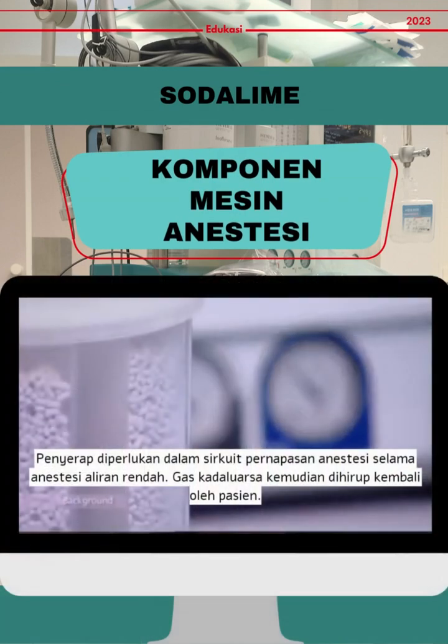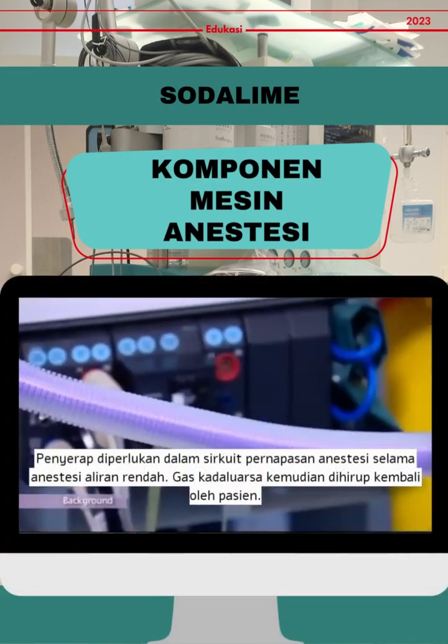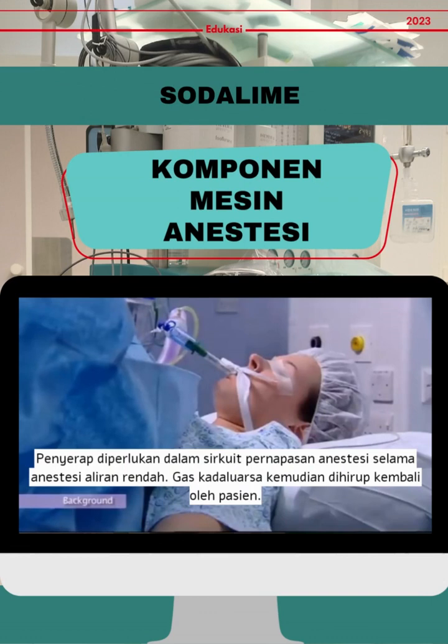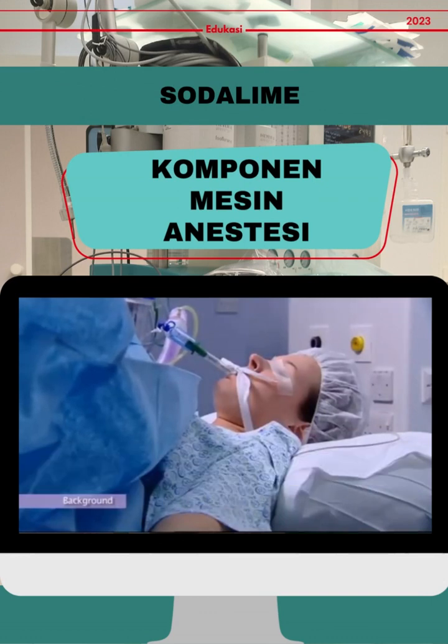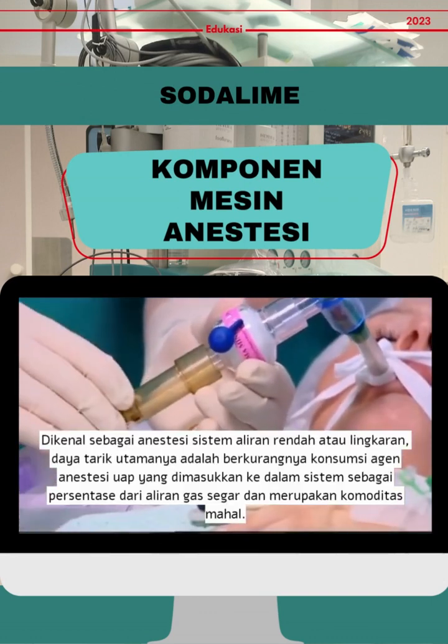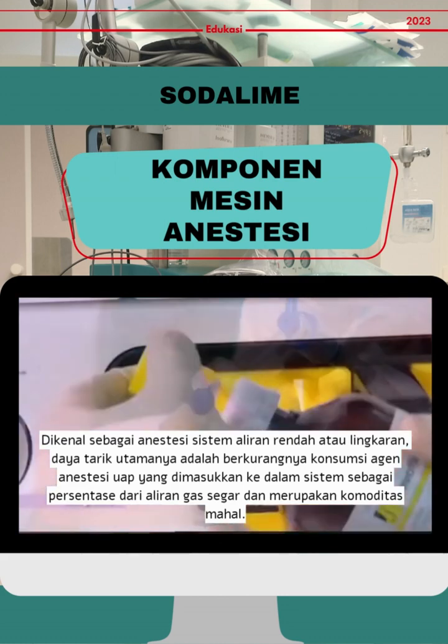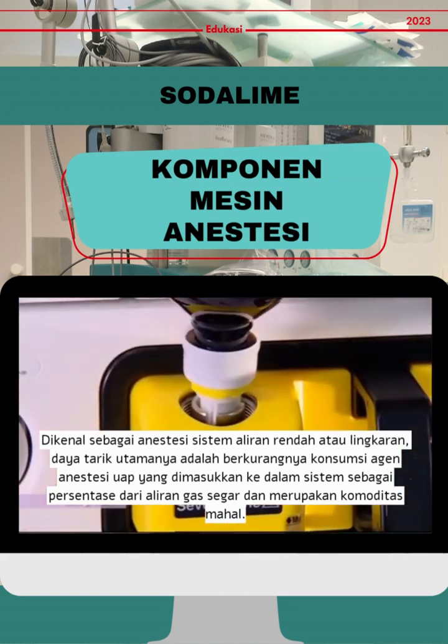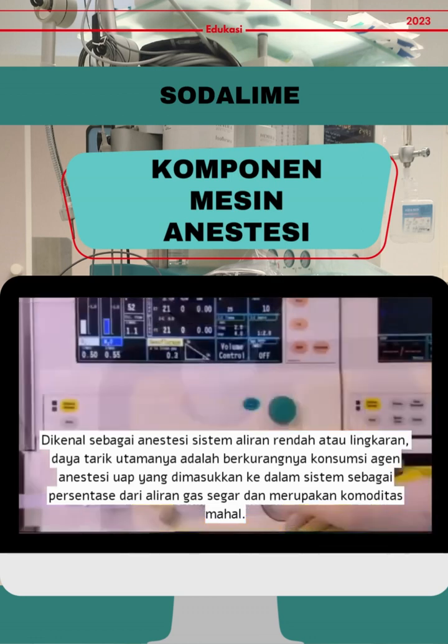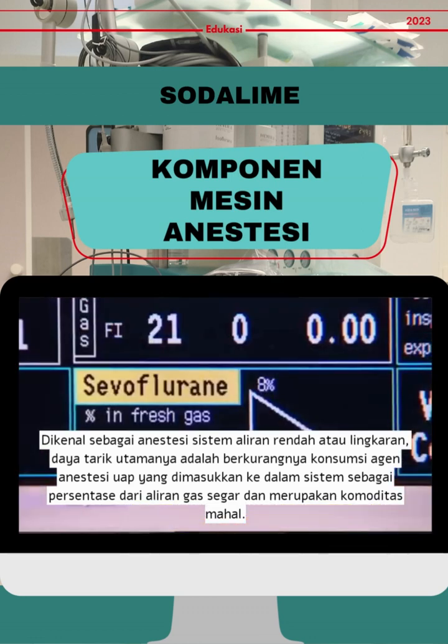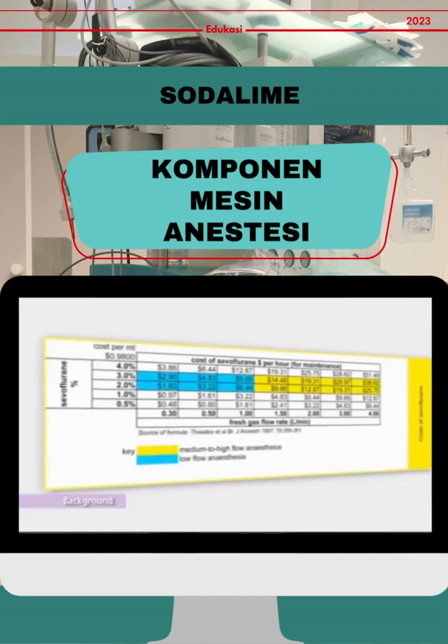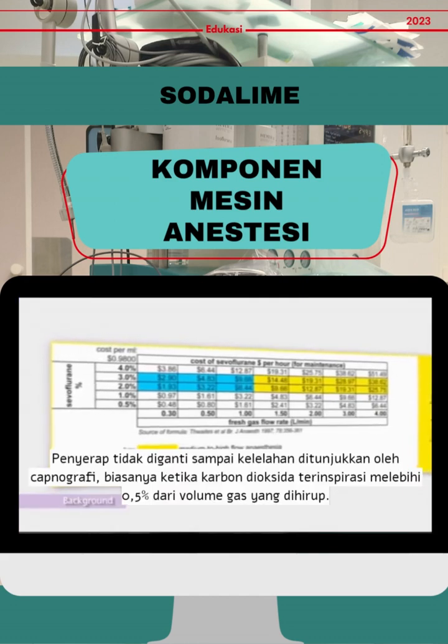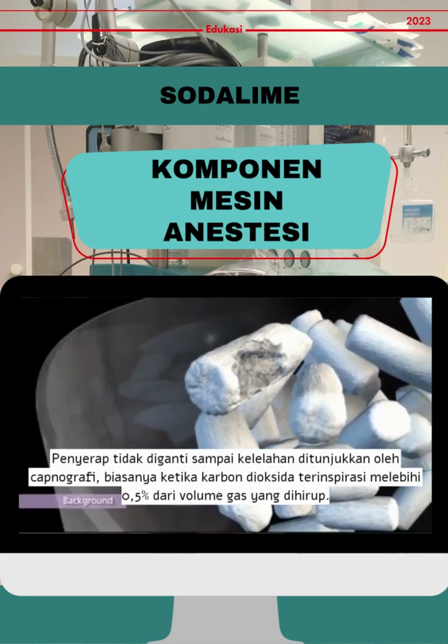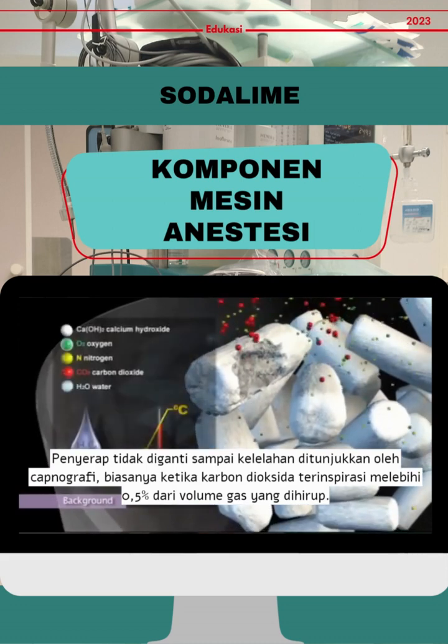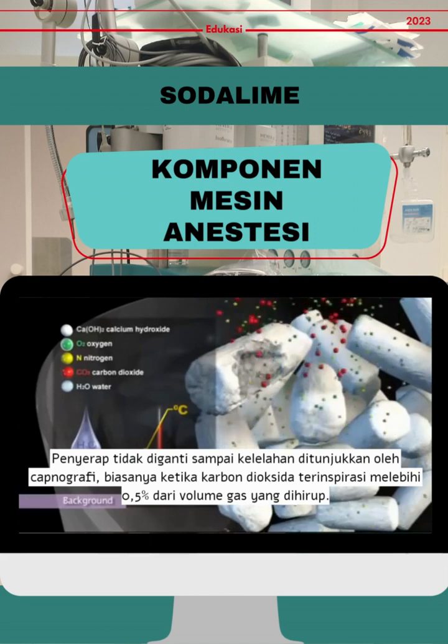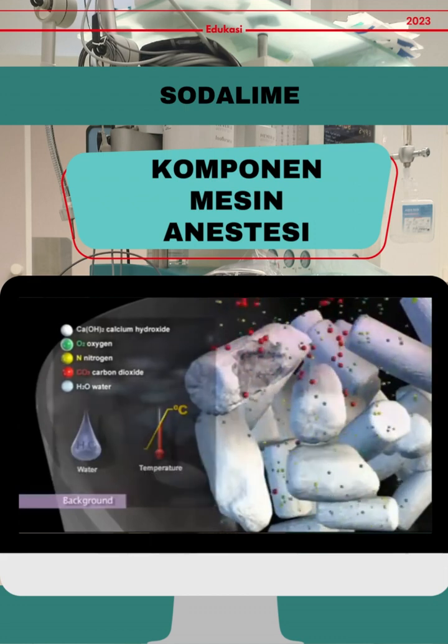Absorbent is necessary within an anesthetic breathing circuit during low-flow anesthesia. Expired gases are then rebreathed by the patient. Known as low-flow or circle system anesthesia, its main attraction is reduced consumption of vaporous anesthetic agents that are dosed into the system as a percentage of fresh gas flow and are an expensive commodity. The absorbent isn't replaced until exhaustion is indicated by capnography, typically when inspired carbon dioxide exceeds 0.5% of the inhaled gas volume.